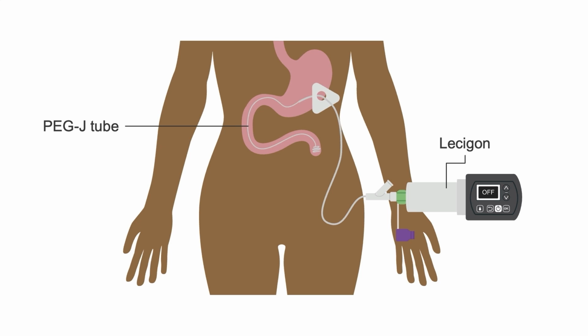The medication, Lecigon, is contained in a cartridge that is connected to the pump. The pump allows Lecigon to be delivered regularly and continuously directly into the intestine. A test is first performed in a hospital via a nasogastric tube to determine the effectiveness of the drug. After successful testing, the PEG-J tube is placed. The pump is programmed in milliliters per hour. Up to 3 different flow rates can be programmed. You can choose the continuous rate during the day, and a morning dose can be programmed independently of the bolus.